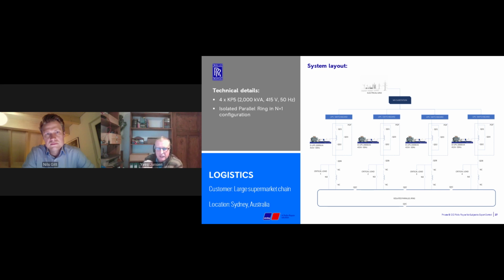So here, what was the challenge? If we want to place 4 dynamic UPS of 2000 kVA into parallel, we will reach a fault level that can exceed the short circuit withstand of the switchgears. So the fault level of 4 dynamic UPS of 2000 kVA will be above 120 kA. That means that we have a limitation on low voltage of the number of machines that we place into parallel. And this limitation is not due to the technology of the dynamic UPS, but the technology of the switchgear that is available on the market.